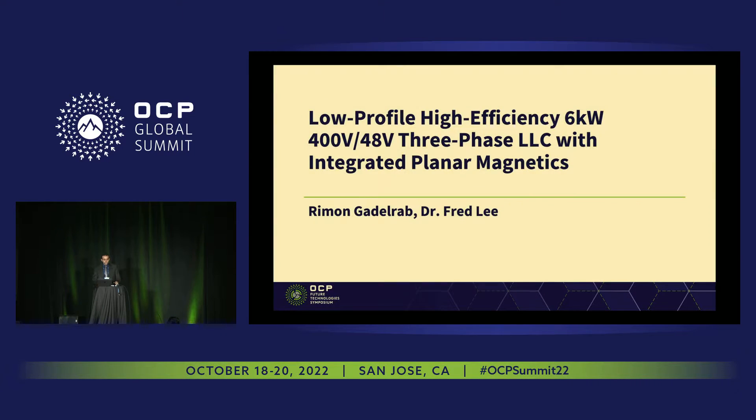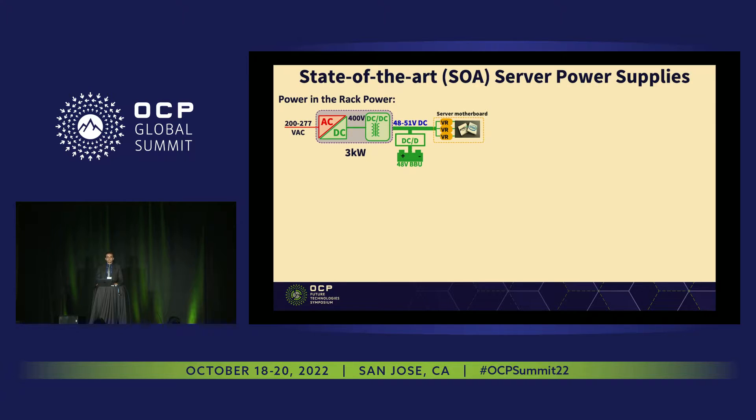Today we're going to talk about low-profile, high-efficiency, 6 kilowatt, 400 volt to 48 volt, three-phase LLC with integrated planar magnetics. We start with the state-of-the-art server power supply. It has two stages: the first one is the PFC, AC to 400 volt, followed by the DC-DC converter, which is 400 to 48 volt. Our work today will be focused on the DC-DC converter, the 400 to 48 volt power supply.